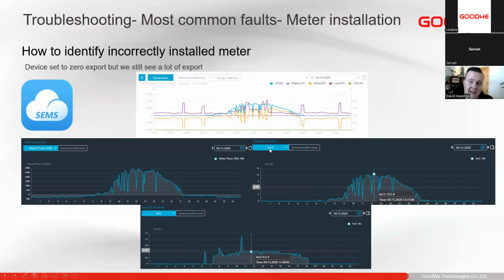But I find on IAC3 that here's all the data that matches that output. So what happened is we rectified the phase rotation error on the inverter, but we didn't change it on the smart meter as well. So the inverter sees loads on phase 3, it produces, but it's metering it on phase 2. So then it just gives the maximum it can, because no matter what it produces on that phase, it's not reducing the consumption on that phase. And then we see export.